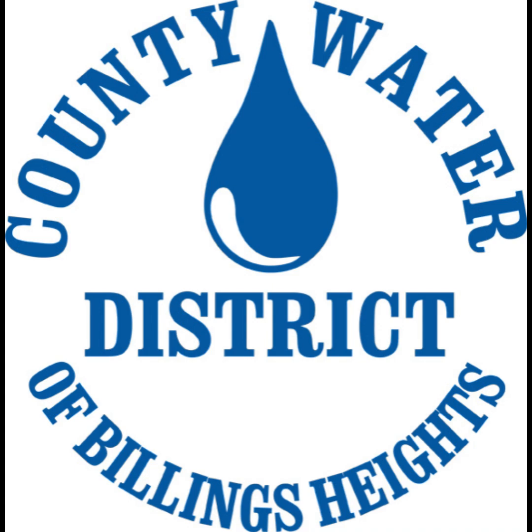All right, does that take more pumps than we have, or did the pumps do that? It would require more pumps. Probably reconstruction of the pump station. Total expansion, reconstruction of the pump station? It is old. I would anticipate some upgrades will be required. Most likely total, because you're pushing through a 6-inch header.